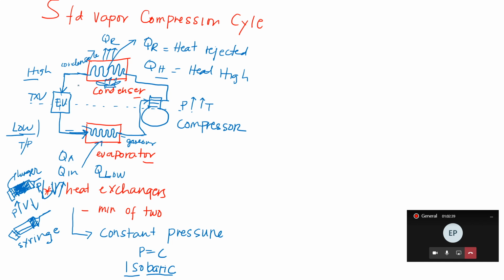The pressure is going down. The volume is up, meaning expand. That's why it's called thermo expansion valve. By way of expanding the gases, the pressure is lowered, because we can only put low pressure in the evaporator. Look at this: low side, high side.